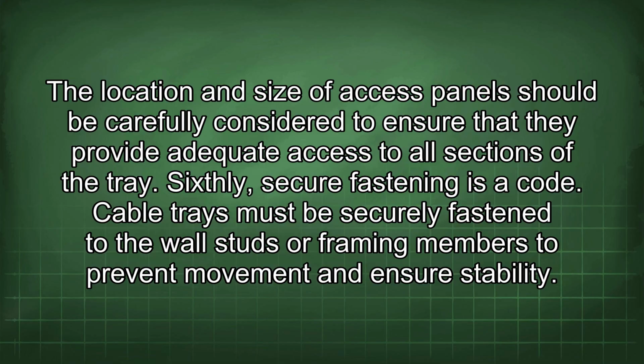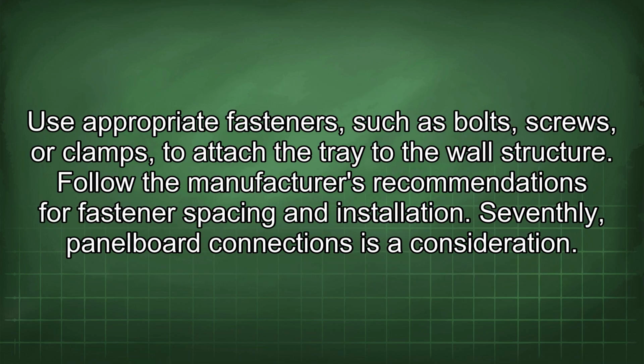Sixthly, secure fastening is a code requirement. Cable trays must be securely fastened to the wall studs or framing members to prevent movement and ensure stability. Use appropriate fasteners, such as bolts, screws, or clamps to attach the tray to the wall structure. Follow the manufacturer's recommendations for fastener spacing and installation.